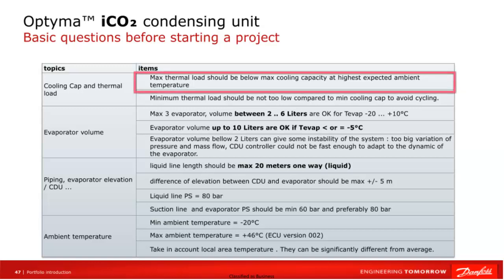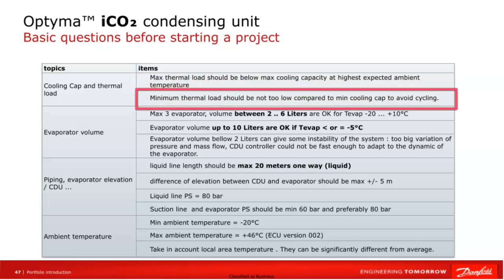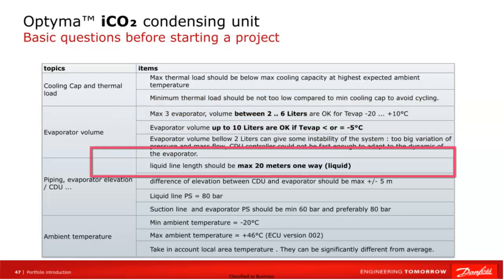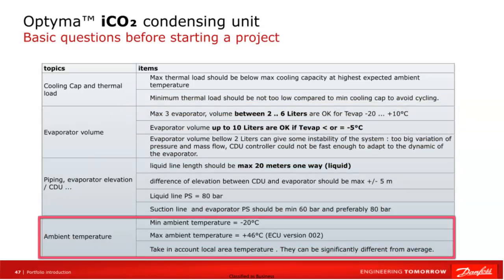Performance and thermal load. The maximum system load must not exceed the maximum capacity of the condensing unit at the highest expected outdoor temperature. The minimum thermal load should not be too low compared to the minimum cooling capacity of the condensing unit, to avoid frequent switching on and off of the unit. Ambient temperature. The ambient temperature must be taken into account when determining the capacity of the condensing unit, as it may differ from the average values.